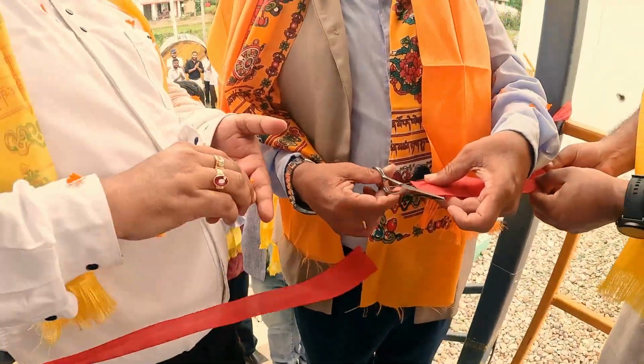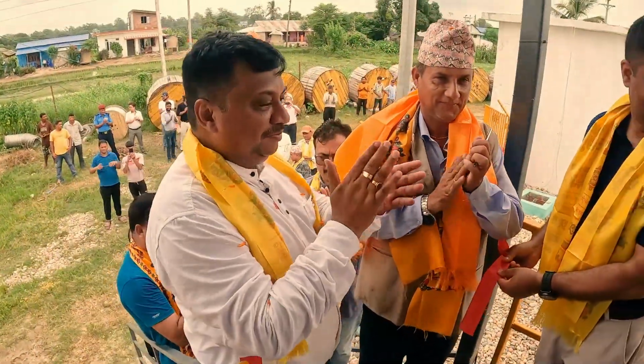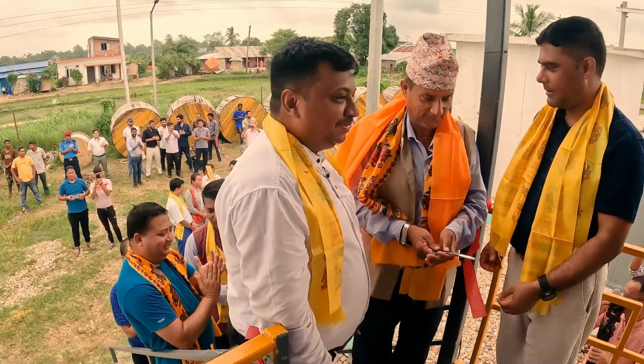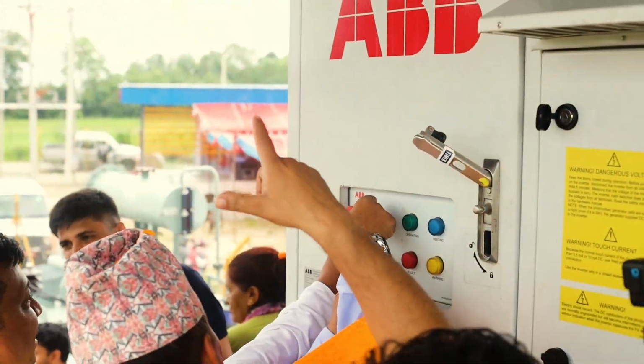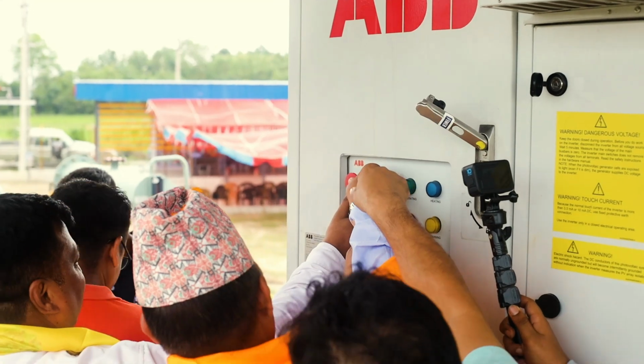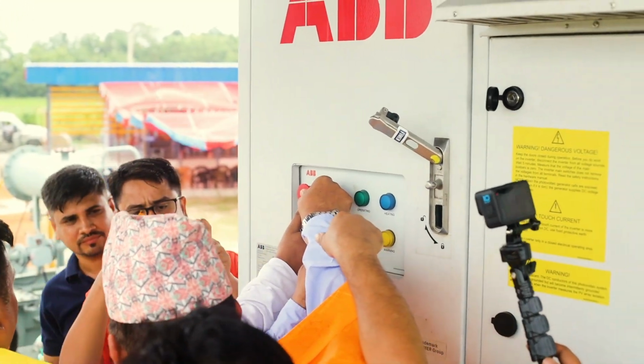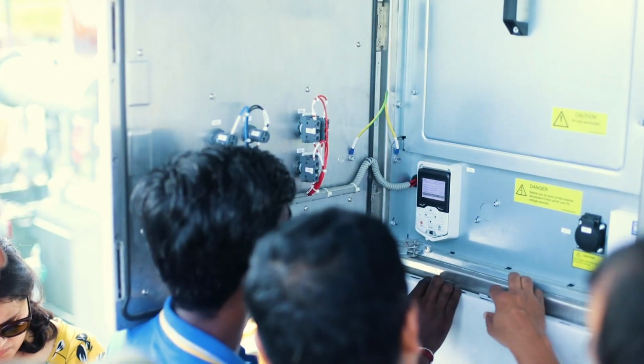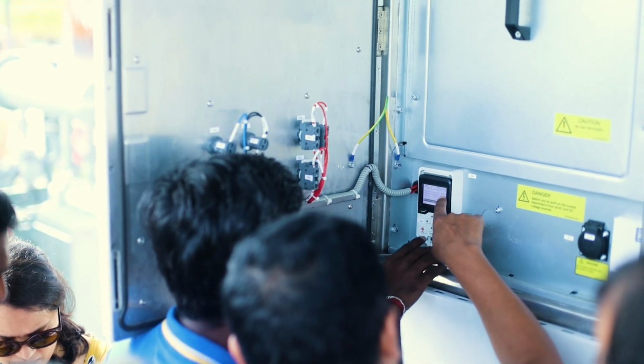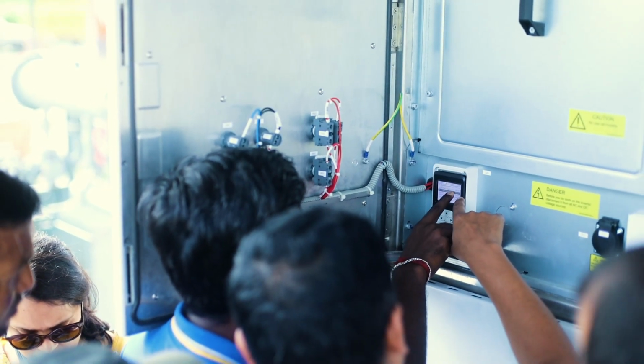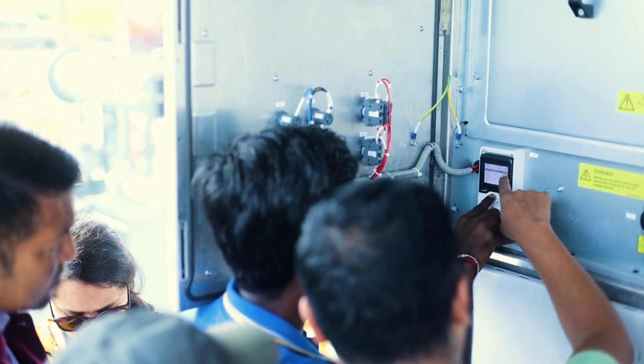The aggregate DC energy produced by the PV panels is converted into AC energy using 1 ABB central inverter of capacity 1.4 megavolt ampere. The output voltage from the inverter, operating at 98.6% efficiency, is 690 volt AC.